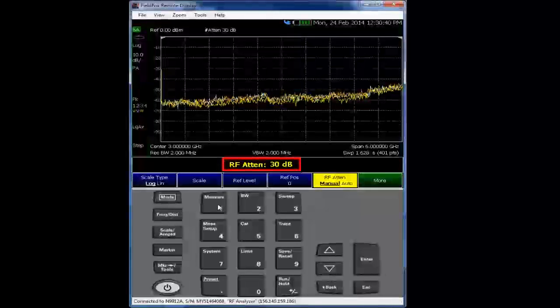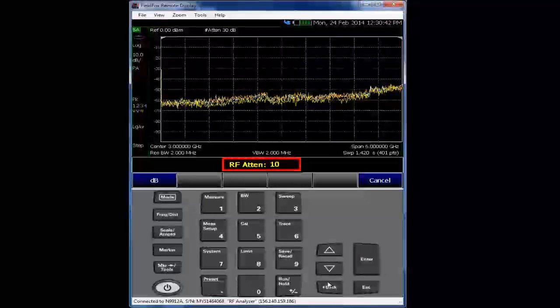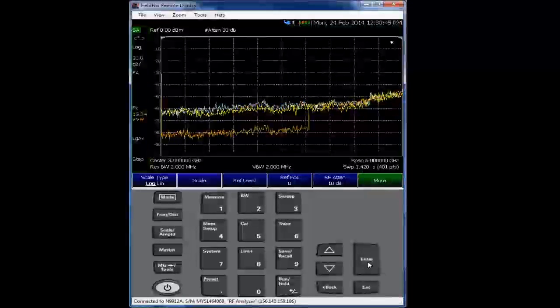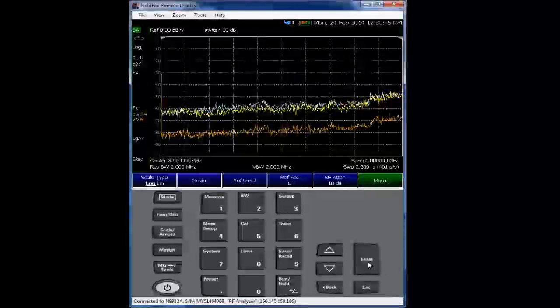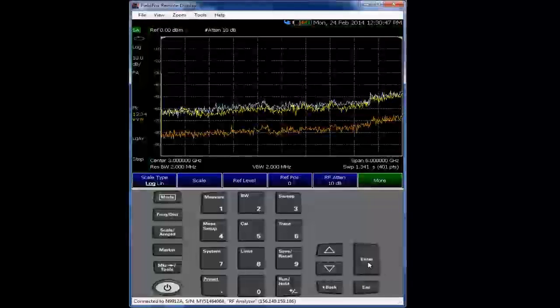So right now, we're going into the scale amplitude, and we're entering the RF attenuation to 10 dB. This is trace three, and you can see the noise floor has dropped down significantly as one would expect.